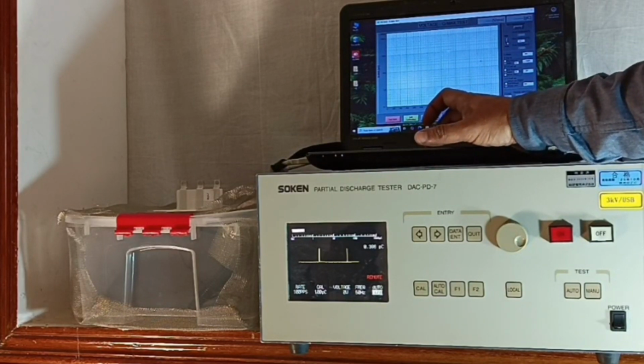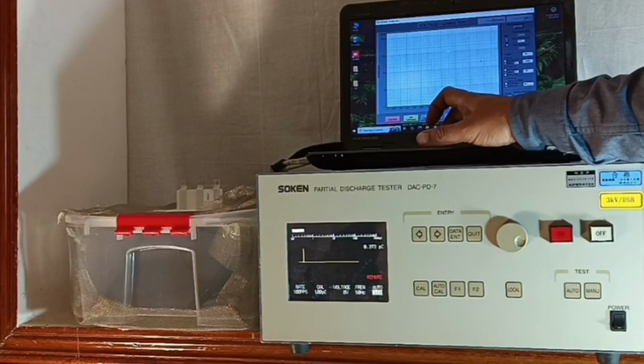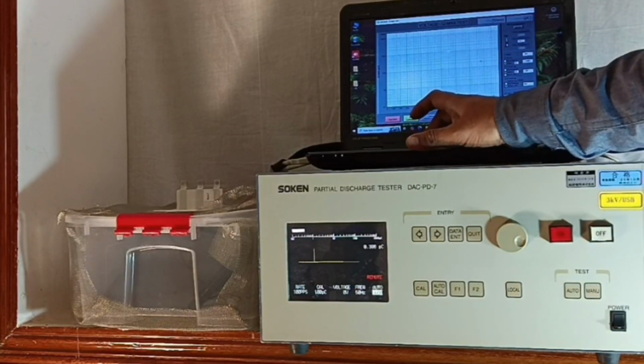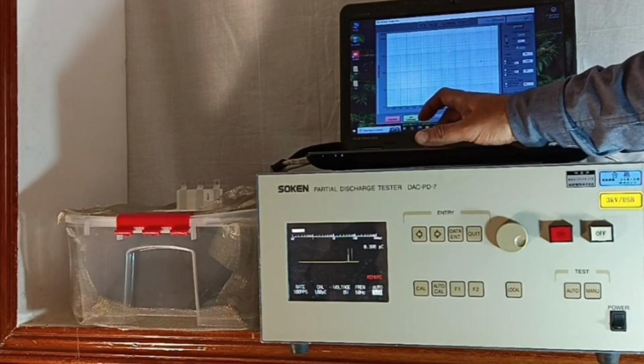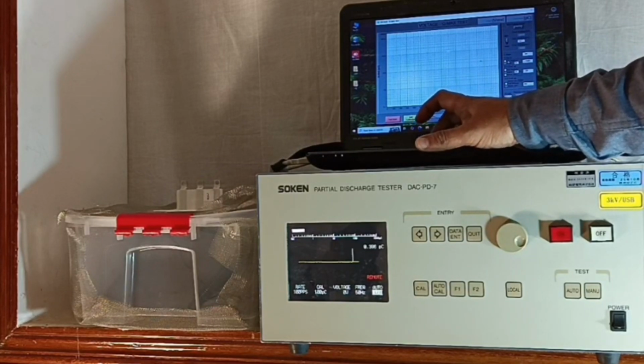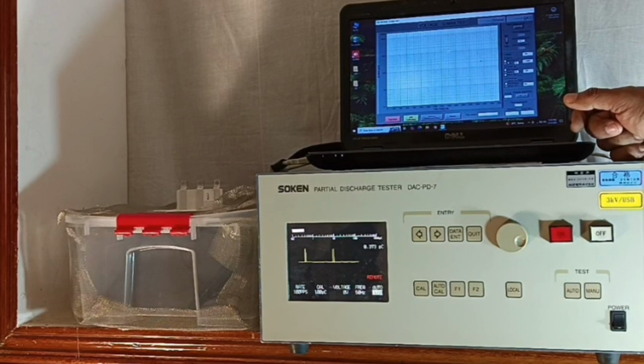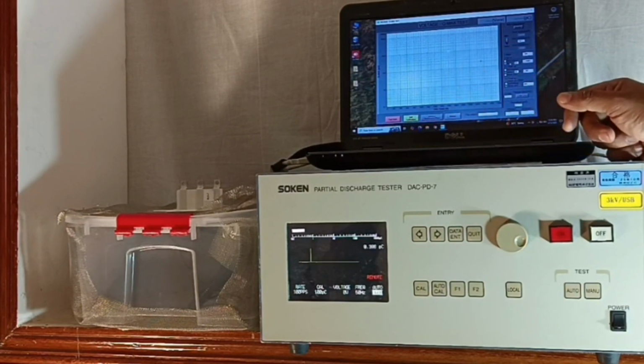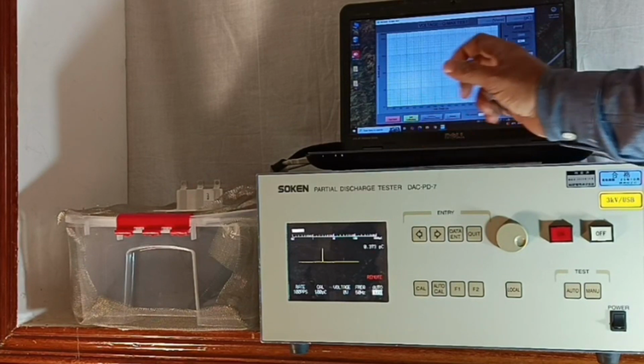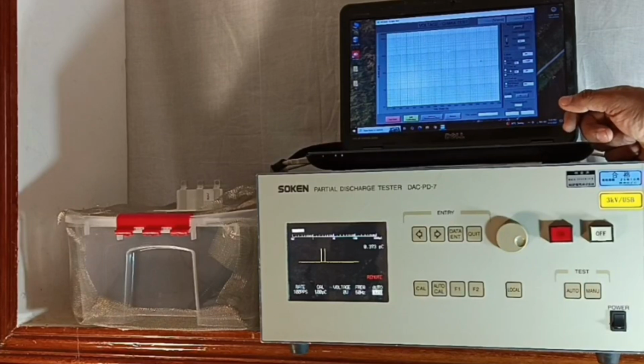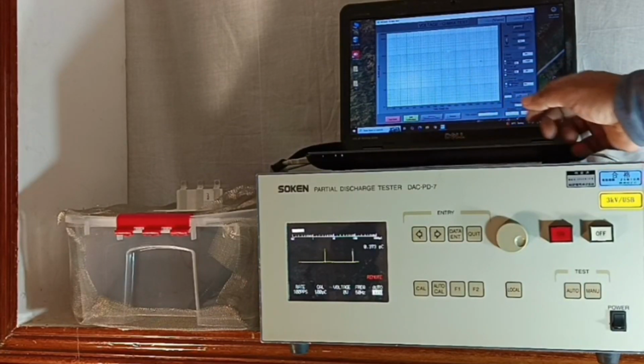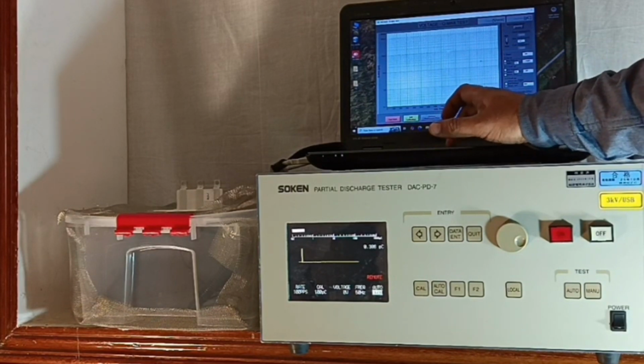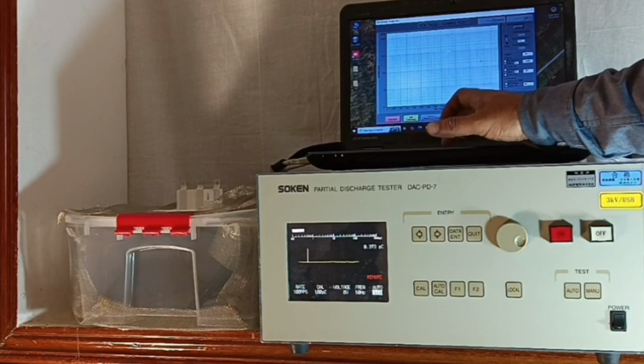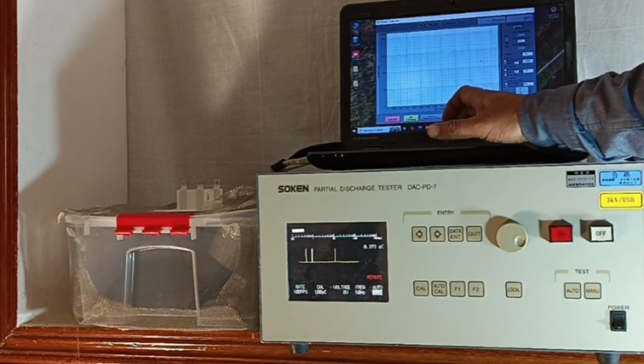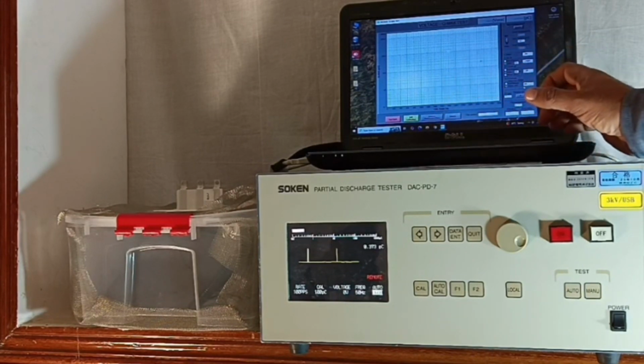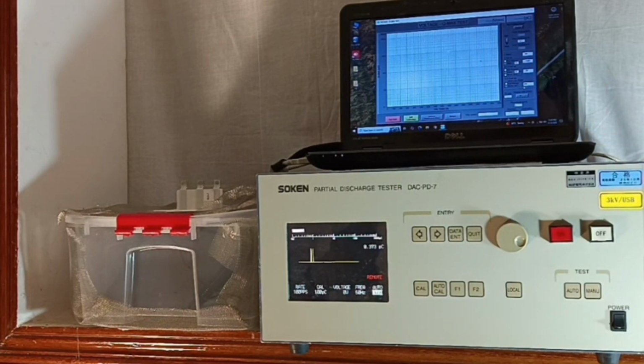We have a RMS or peak selection for the display of voltage. Threshold of 3 kV is possible with this, maximum voltage of 3 kV. Then the start voltage, you can define this maximum voltage can be set. We have set now PDIV plus 10%. Then the extinction voltage minus 20% is set, and the end voltage is set, and the rate of rise is set as 10 volts per second. You can have 25 volts, 50 volts, 100 volts. The threshold of 4 PC is set.